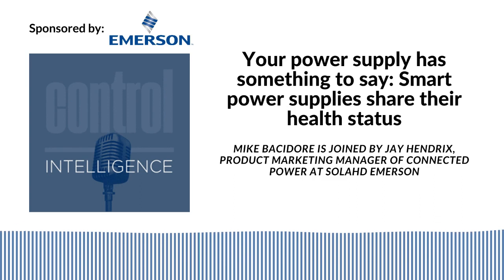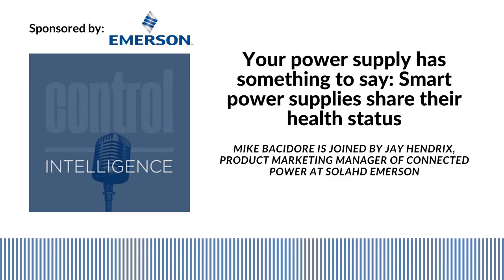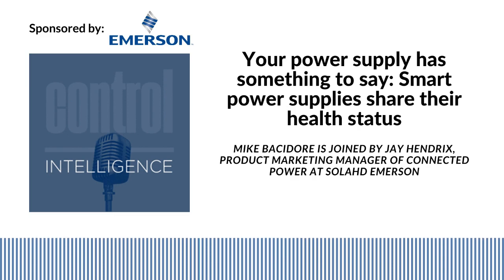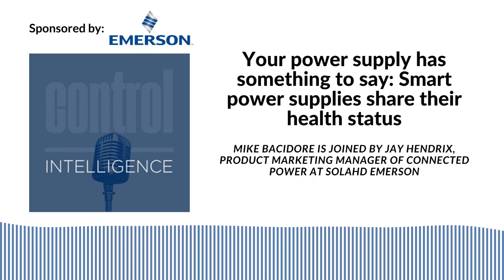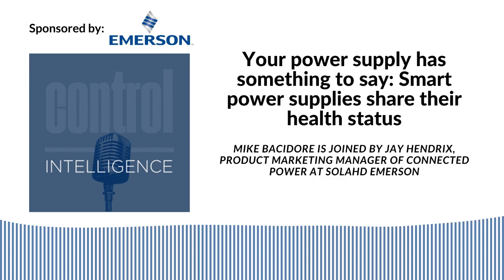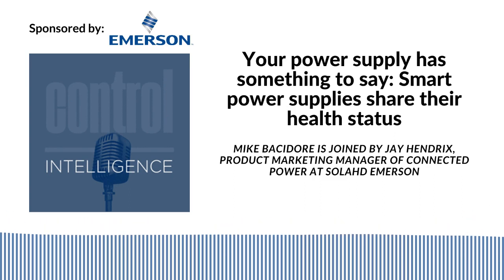Yeah, so really the life of a power supply is going to be affected by how hard it's been used. So how hard it's been loaded over time, and its environmental temperature, the temperature it's been operating in. So we might call that stress, how hard the power supply has been stressed. And you never know, depending on the situation and the customer, how that might change based on its usage within that environment. Mm-hmm. So the things that really drive a power supply's life are stress, which is load and temperature.